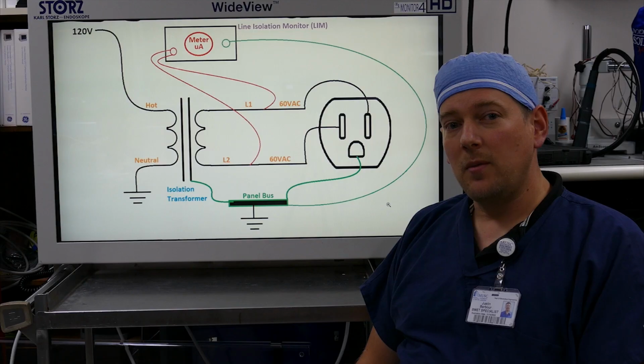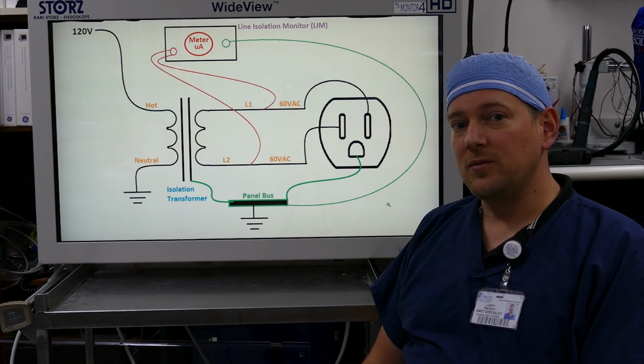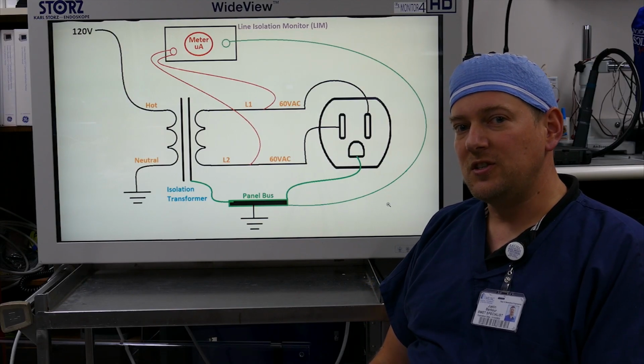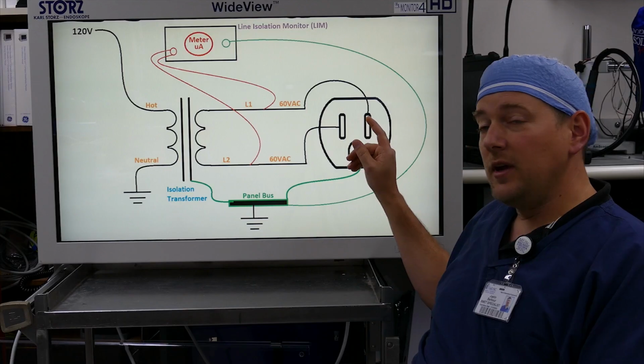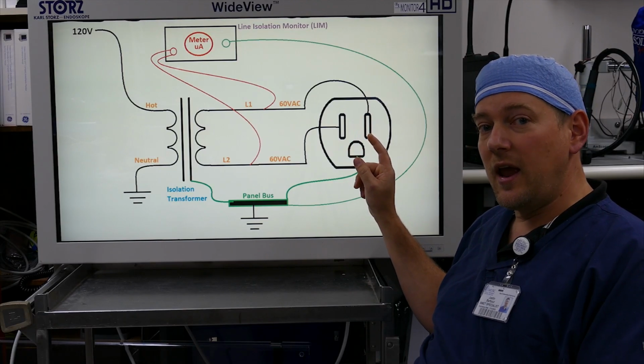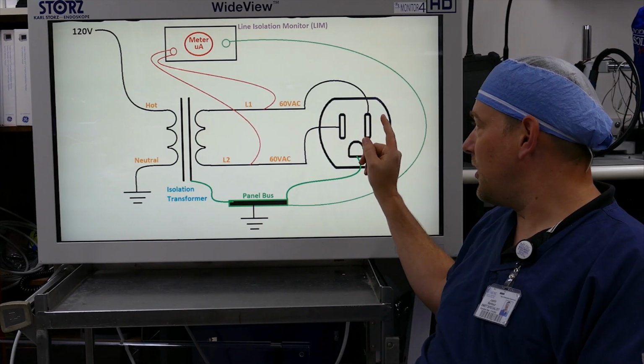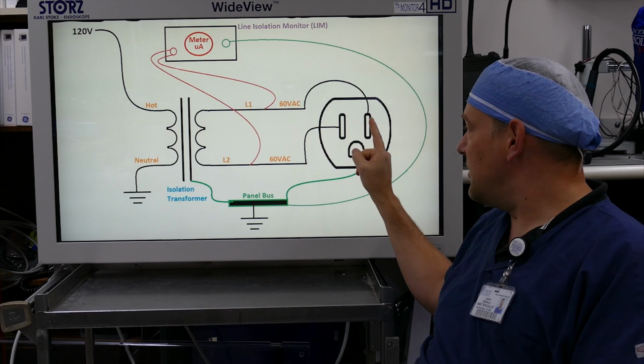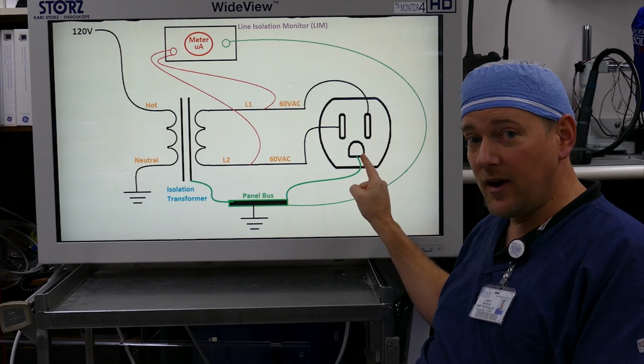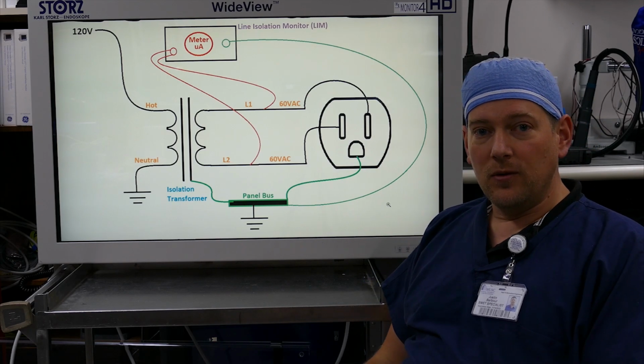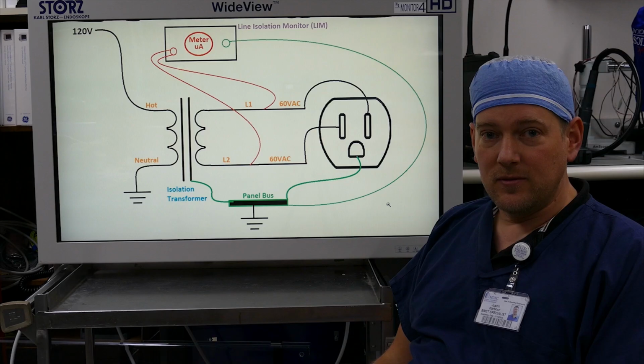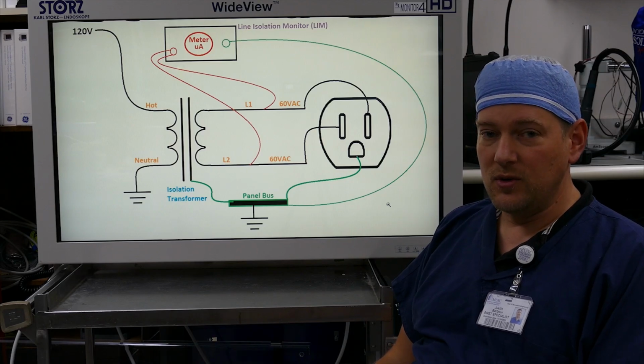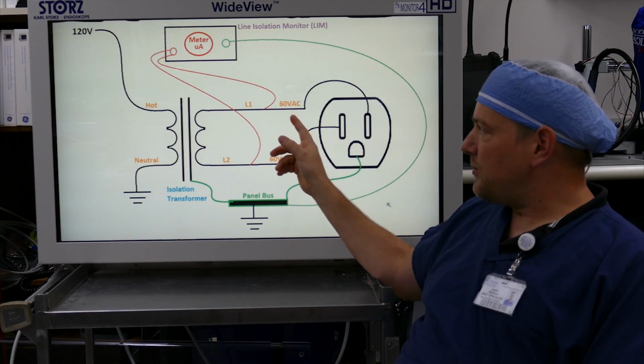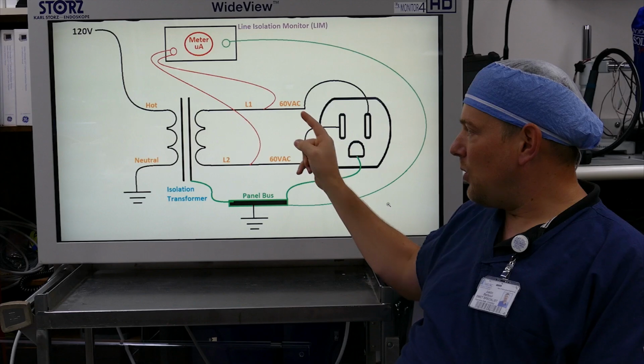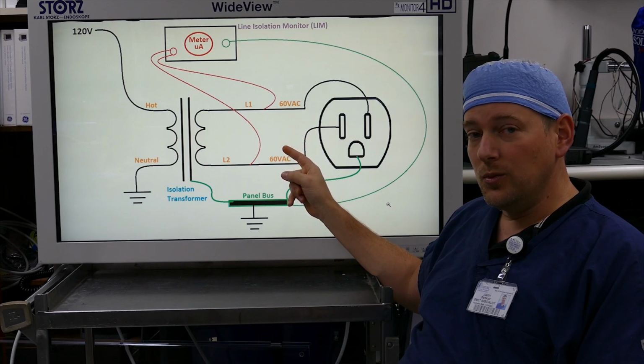This presents some problems for biomeds in operating rooms. When you're doing your electrical safety checks, normally electrical safety meters and electrical checkers are looking for 120 volts on one leg, neutral on one leg, and ground on a leg. So it'll give you a fail result on your electrical safety. So you have to be a little intuitive when you're doing these tests. If you're in the operating room and you happen to touch L1 or L2, you will not get shocked.